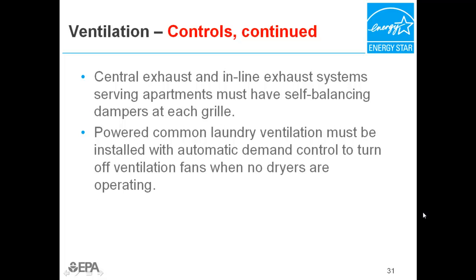These ventilation control requirements are also just applicable to projects in the prescriptive path. Central exhaust and inline exhaust systems serving apartments must have self-balancing dampers at each grill. These dampers prevent the stack effect from impacting the amount of ventilation exhausted from the space by automatically moderating how much air can be ventilated through the grill.